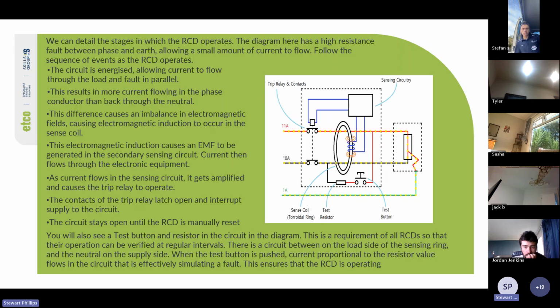Cool. We can detail the stages in which it operates. The diagram here has a high resistance fault between phase and earth, allowing a small amount of current to flow. So following the sequence of the events, the RCD operates. The circuit is energized, allowing current to flow through the load and fault in parallel. The result is more current flowing in the phase conductor than back through the neutral.